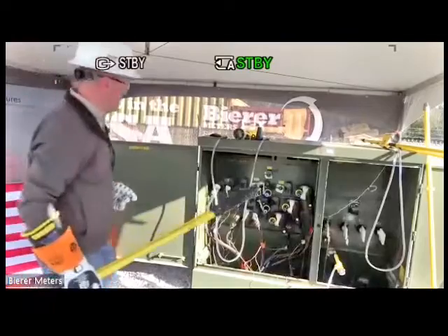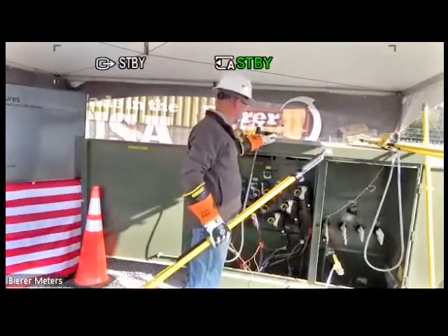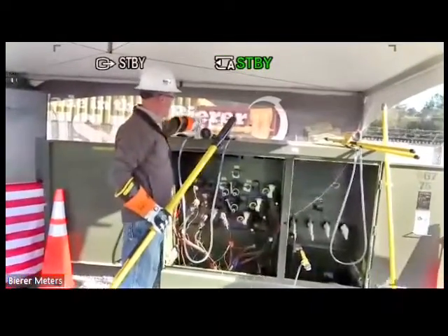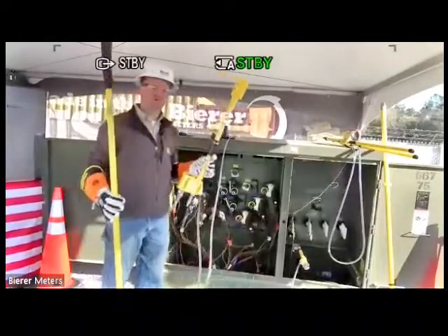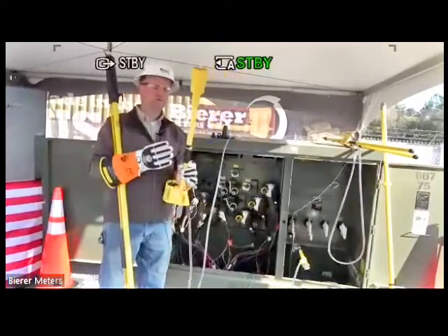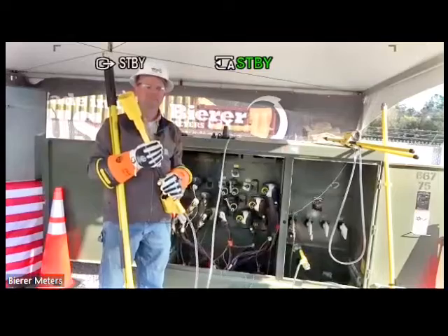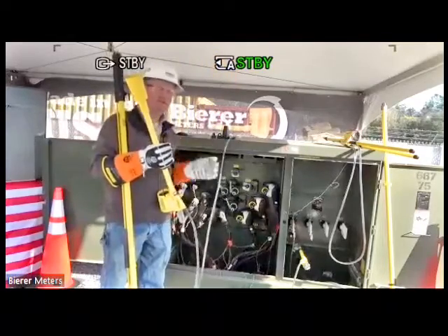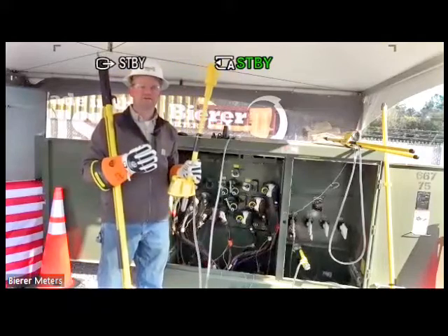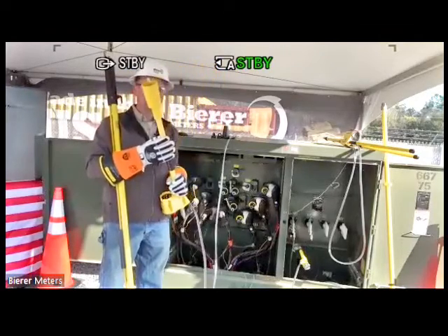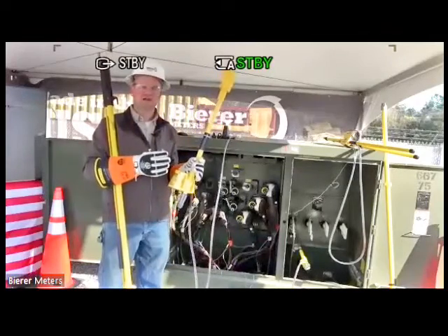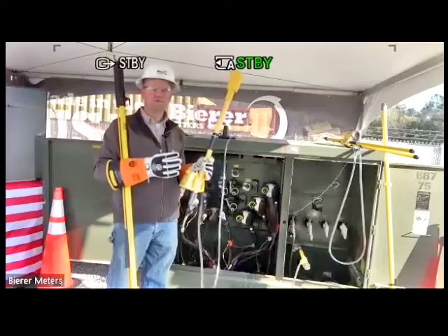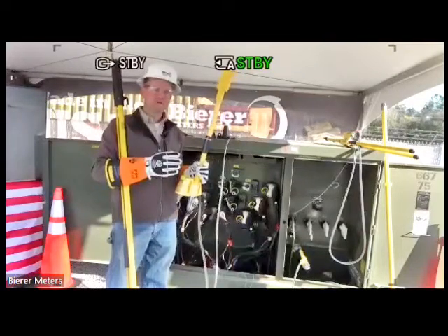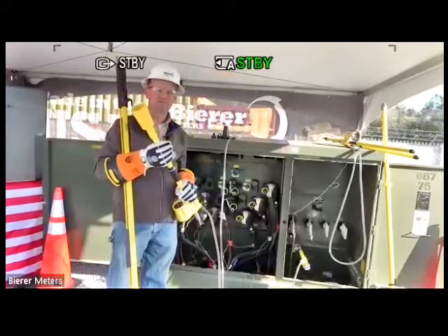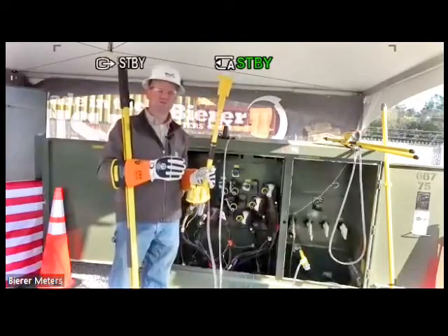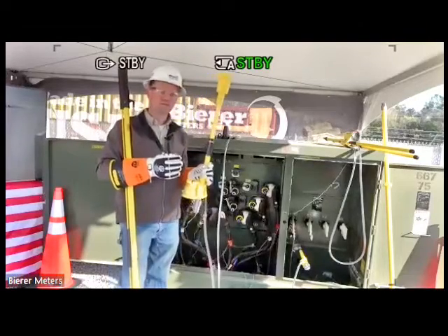So again, with high potting primary cable, as I just mentioned, I want to always put my high pot to the energized source. We do commonly get the question, does it matter where you put the high pot adapter? Should I attach it to the meter or to the second probe? And the answer is it doesn't matter. I just get used to attaching it to the meter out of habit, and I'm consistent with that. So whichever way you're more comfortable, whichever way makes more sense, you can do it either way. Just make certain that whichever probe you attach the adapter to, you always take that to the source. The high pot always has to go to the source cable.